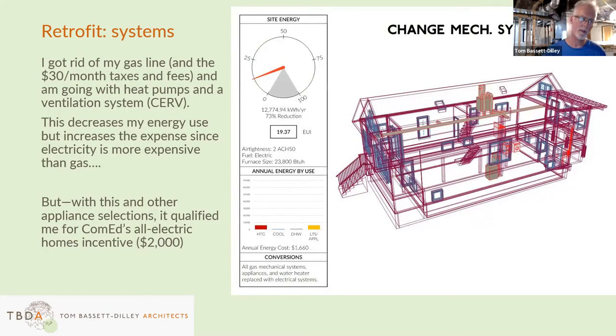Finally, after all that thermal envelope stuff is done, we change out the mechanical systems. It's interesting—you'll notice the furnace size went from 22.6 to 23.8. That's because I'm ventilating: I'm getting an ERV in here, and ERVs bring in fresh air and extract stale air from the house. There's a bit of an energy penalty for that, even though mine is a CERV, a conditioning ERV, so it conditions the air as it comes in and doesn't feel cool, but it does take a little energy. It's a nerdy point—if people have questions, we can talk about that later.